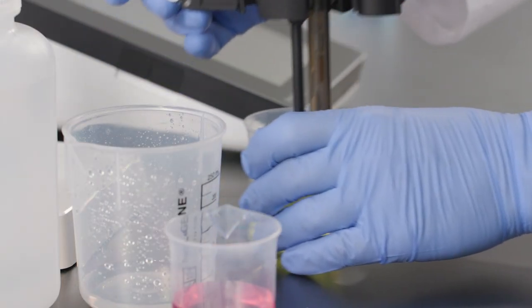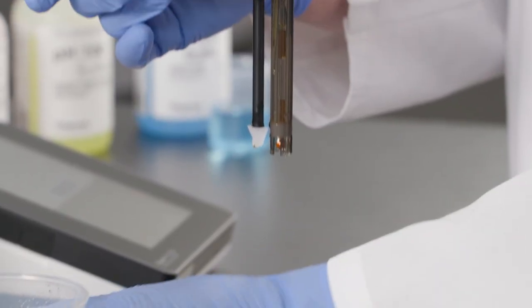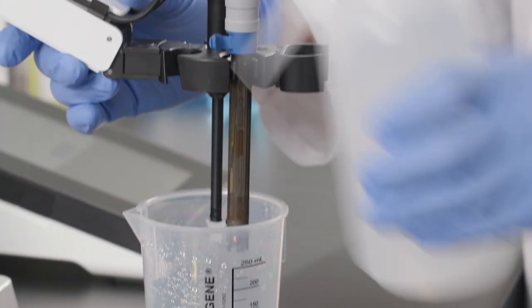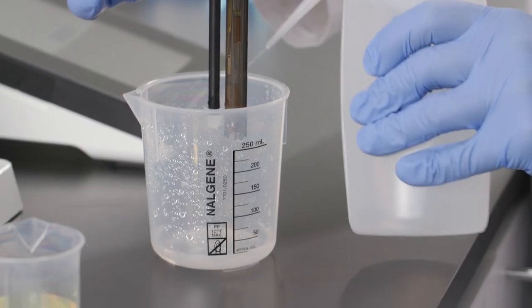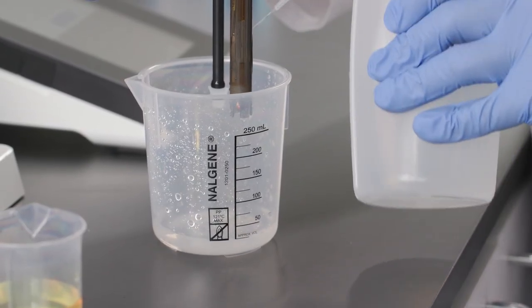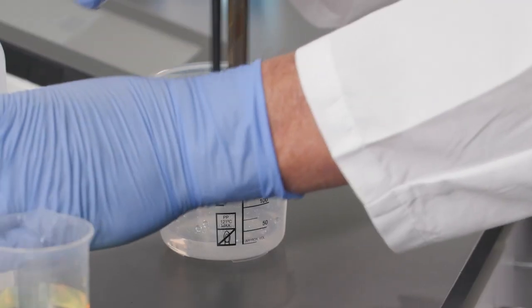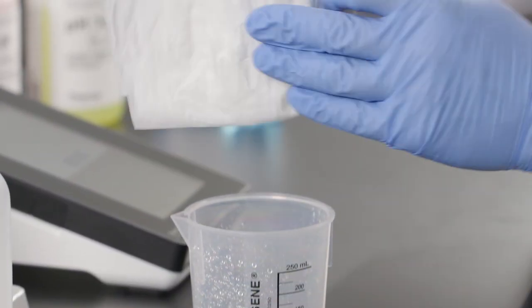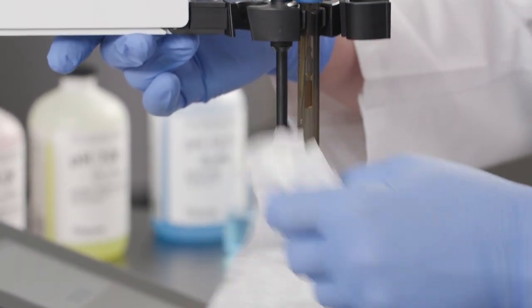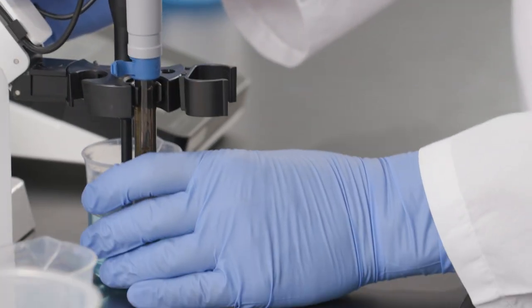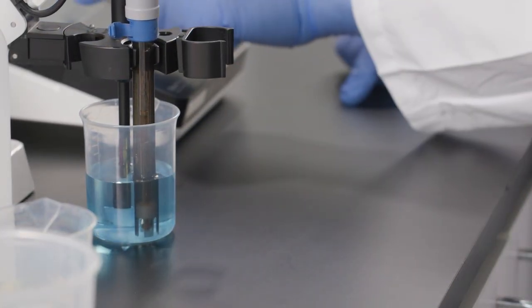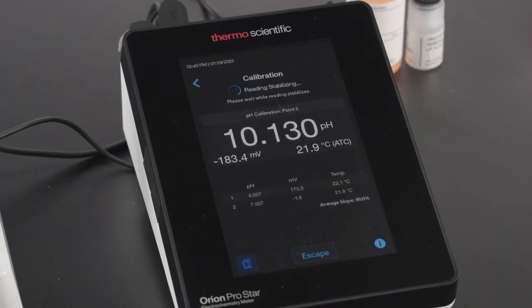We should note at this point that temperature measurement is an important component for accuracy. During calibration, temperature readings are used to assign the correct, accurate pH values to the calibration buffers. For example, a pH 10 buffer has a known value of 10.01 at a temperature of 25 degrees Celsius, but has a known value of 10.06 at 20 degrees Celsius. When measuring samples, temperature readings allow the meter to stay in calibration by adjusting the calibration to match the sample temperature. The meter has recognized pH 10 and it's displaying the known value at this temperature.